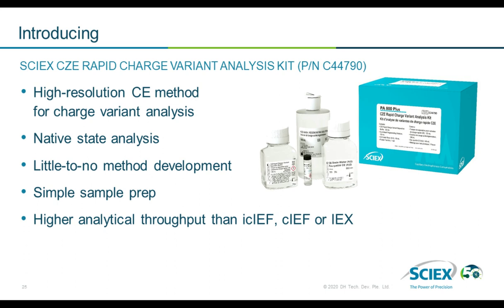And so today, that's what we're introducing. Our new CZE kit for protein analysis, for charge variant analysis. And this is the CZE Rapid Charge Variant Analysis Kit. As you would expect from a CE method, it's very high resolution. And a really nice benefit, in my mind, is that it's done in native analysis. So we're not denaturing, as we generally are in IEF. So we're analyzing the molecule as it is.